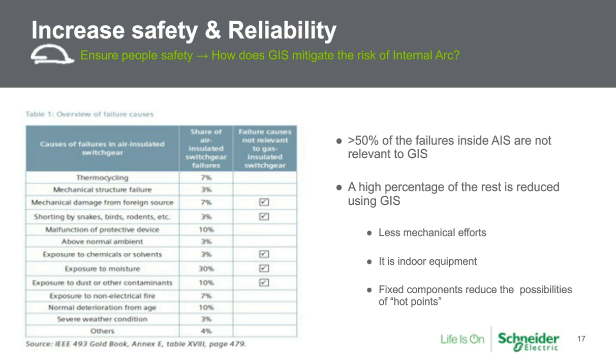So going through a couple points here, exposure to moisture. Because your switchgear, or your medium voltage circuit, your live parts, are sealed in that gas-insulated tank, you have no exposure to humidity or salty or caustic, polluted environments. So you reduce that effect on your switchgear.